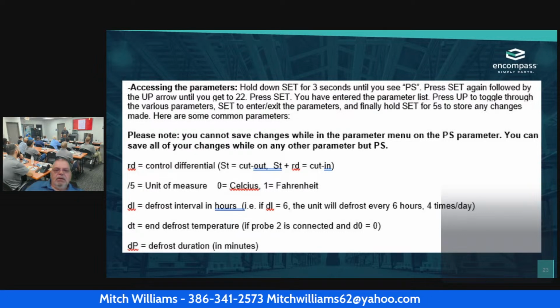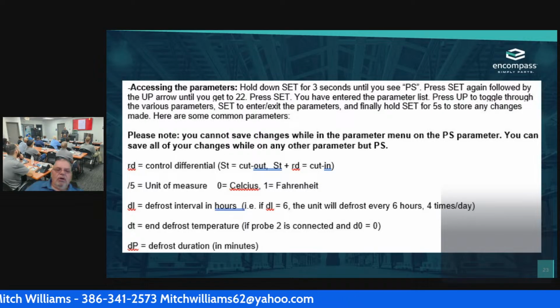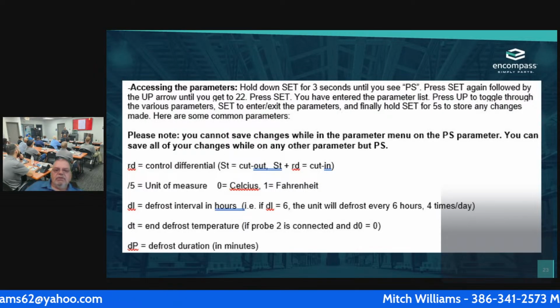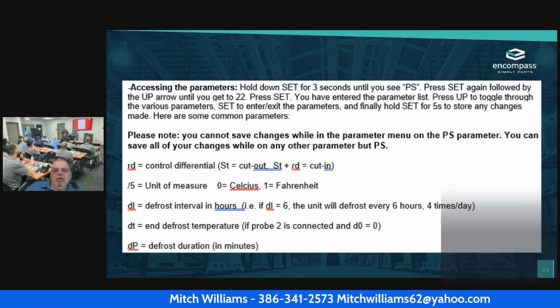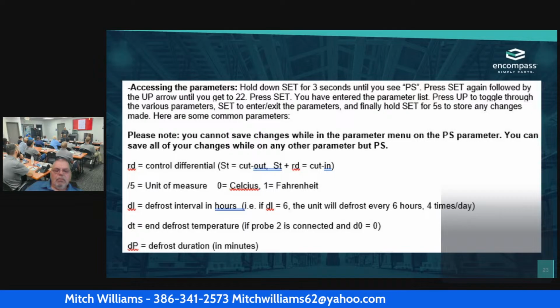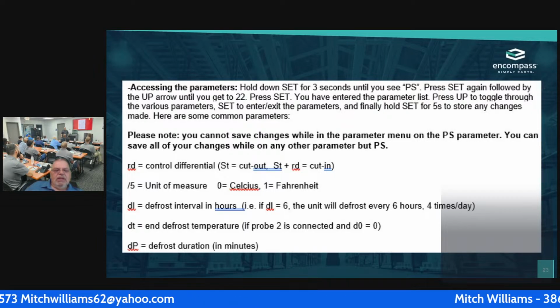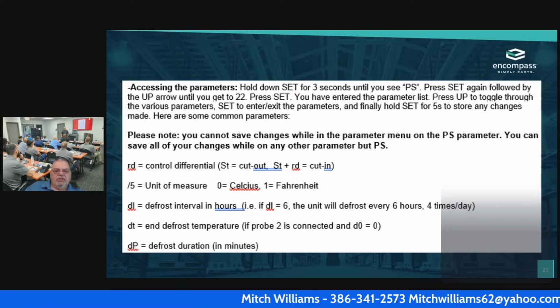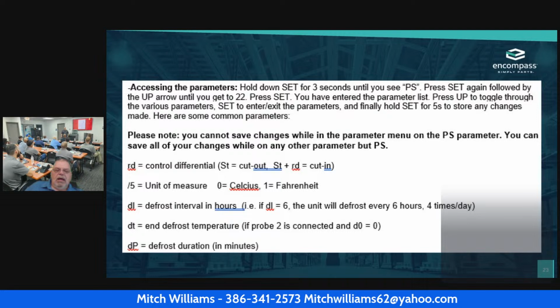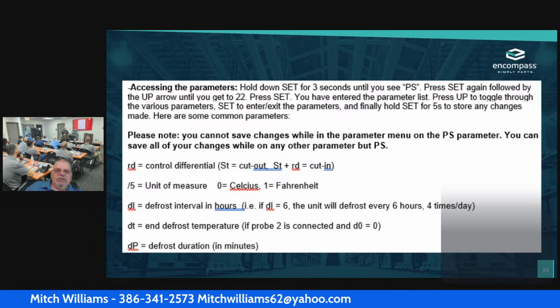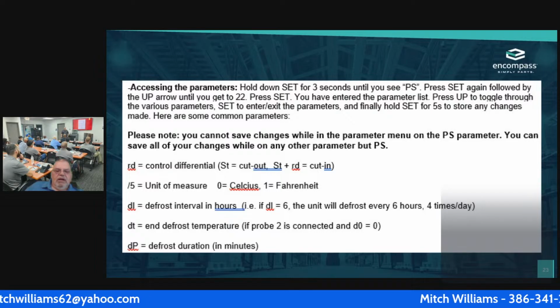Okay. Here are some of the common parameters. RD is the control differential. Okay. Standard is the ST is cut out. The ST plus is the cut in. Once I go scrolling through, my /5 tells me 0 is, if it comes up 0, it tells me it's in Celsius, which is what ours would have done on the one that I just showed you previously. If it's in a 1, it should be in Fahrenheit.